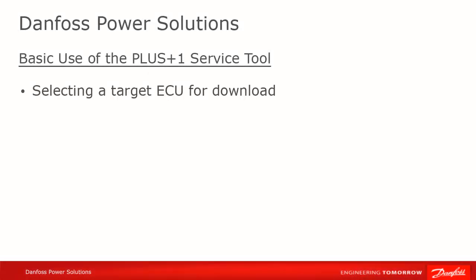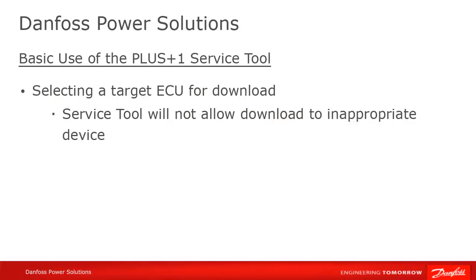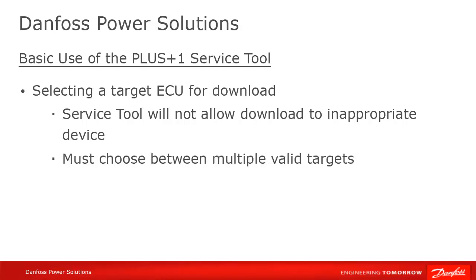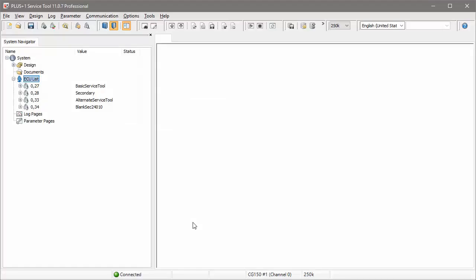The service tool is smart enough to prevent you from downloading an inappropriate application to a device. For instance, you wouldn't be able to download an MC18 application to an MC50 controller — even a wrong model number will prevent download. However, if there are multiple valid candidates for download on the CAN bus, you have to choose the destination at download time.